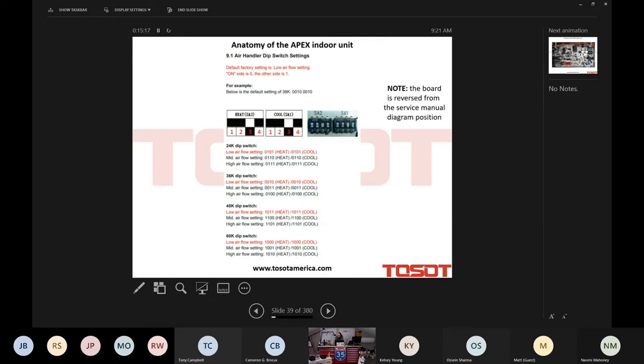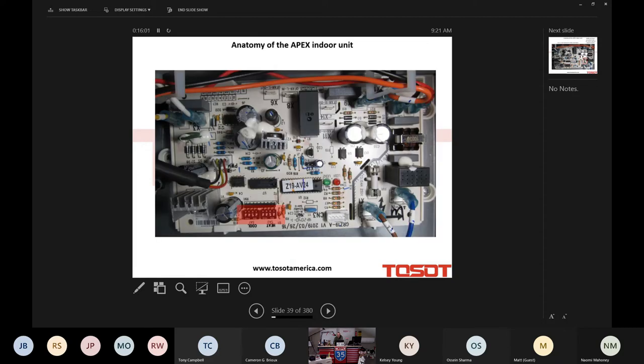The indoor unit, guys, has some dip switches. Here's note number two for the day. Both the Apex indoor and outdoor unit have a series of dip switches which must be set by the installing contractor. They are set on some factory defaults, but there's probably some tweaking that the installer needs to do specific to that application, and we'll talk about that in great detail as we move forward today. But I just want to bring to your attention right now that there are a set of two dip switches, just like you see right here on the indoor unit. And we'll go into great detail as to what they do and how to set them as we move forward.